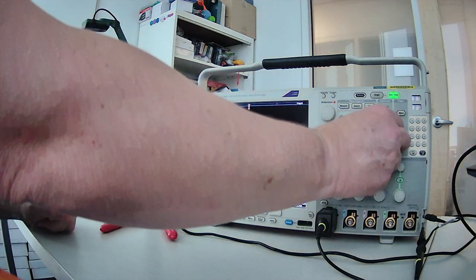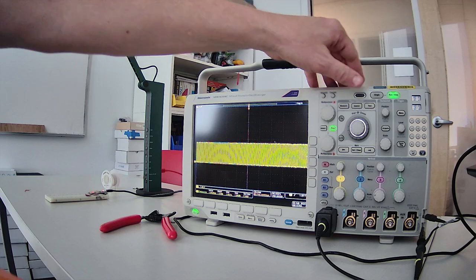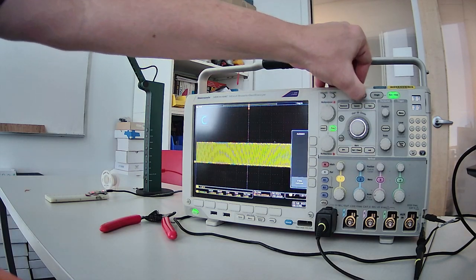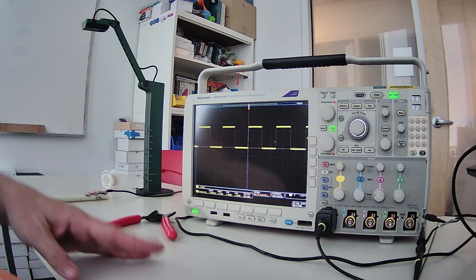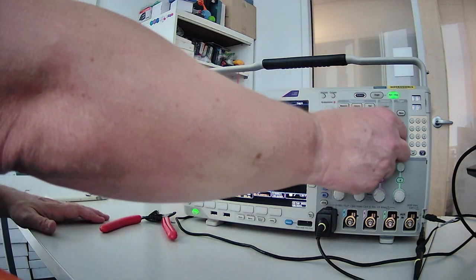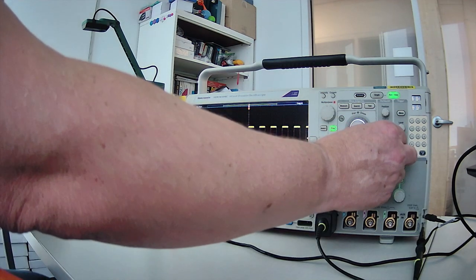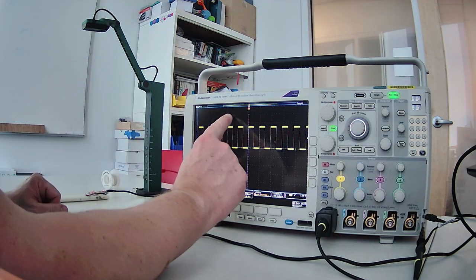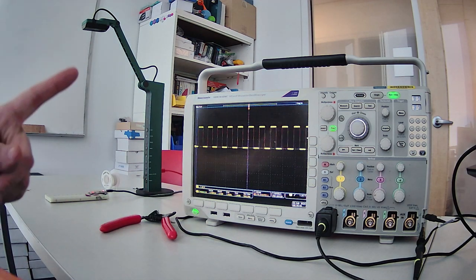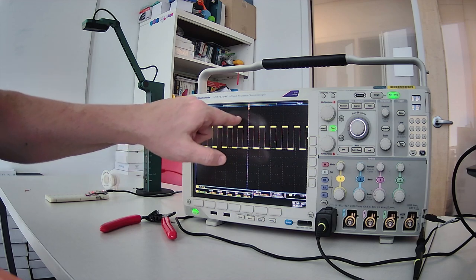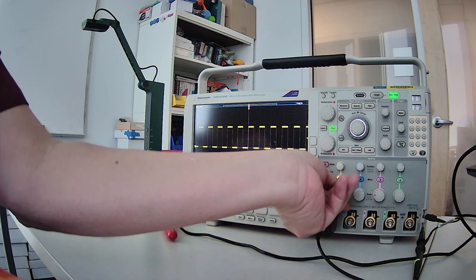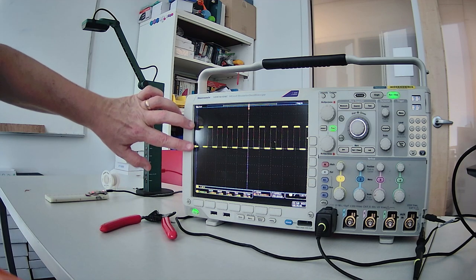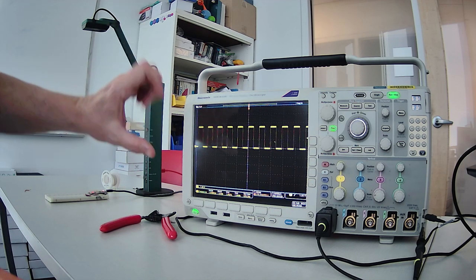But you can always hook it there and you can see the square wave. Now if it's all messed up, you know, if it looks like that, you can hit the auto set button up here and the scope will correct itself and it'll take you to this point. This horizontal scale here sets the time, so how much time each one of these divisions here going right to left, how much these divisions, these horizontal divisions are worth. And then this knob here for each channel says how many volts each division is worth.